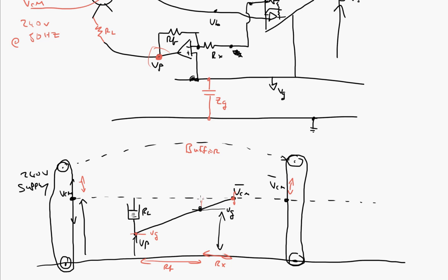So the observed, what we have now is this is the observed common mode. Observed common mode with the driven right leg. So with a DRL, driven right leg. But what we would have had before is this would have been the old, if we had just connected the ground of the amplifier straight to the leg, this would have been the observed. So this is the observed common mode before, so with no DRL. So what we see is we've reduced, using this amplifier, we've reduced the DRL, the common mode seen when we use the DRL. And the reason is using this fulcrum amplifying effect of the inverting amplifier.